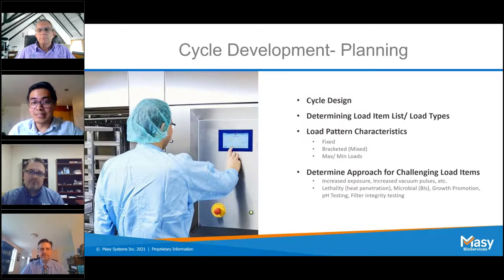When looking into liquid cycles specifically, typically these are a lot easier to develop as you're not dealing with vacuum pulses, and you only need to plan to test your load items based on the exposure time and how long it takes autoclaves to reach the temperature and meet the minimum lethality you need.